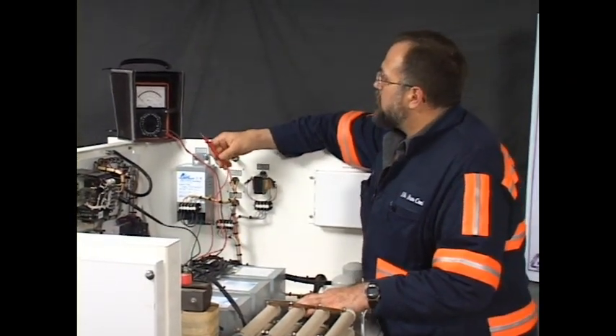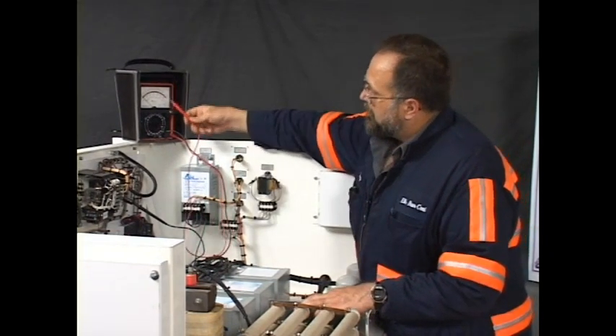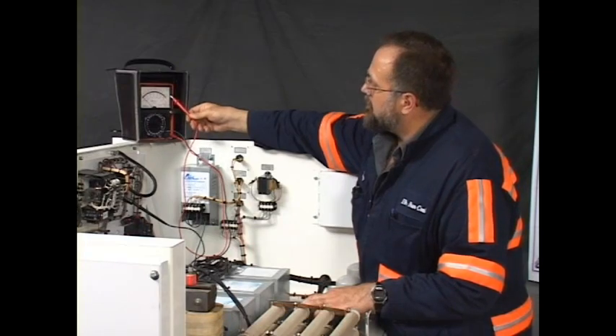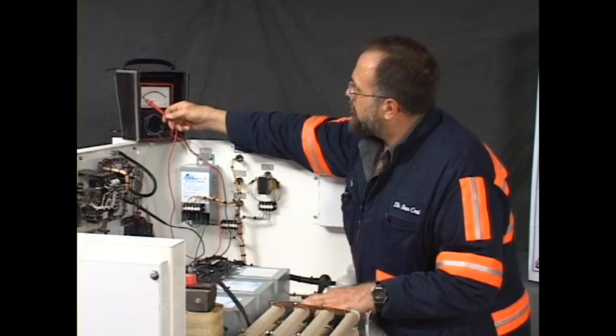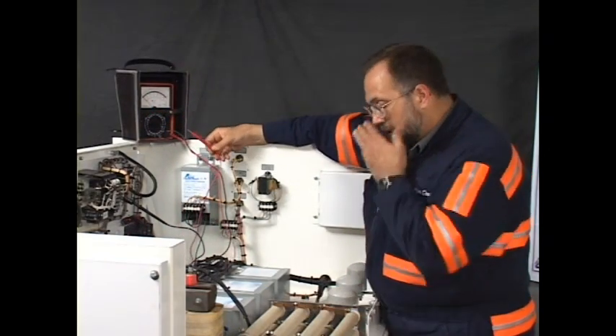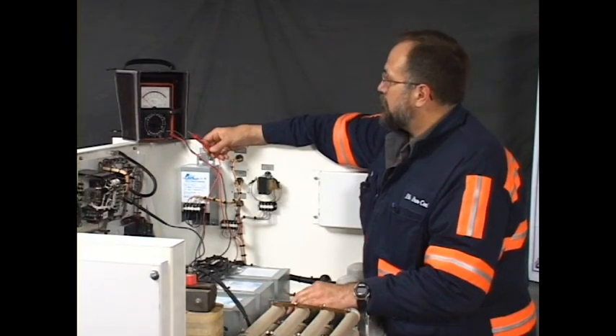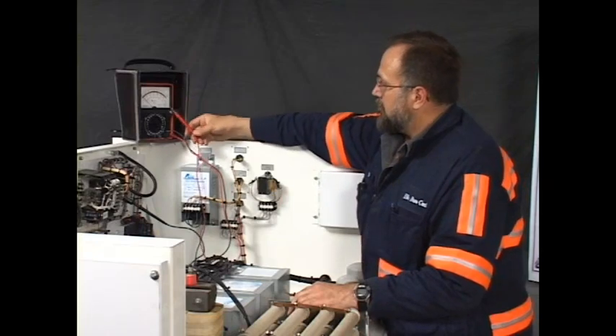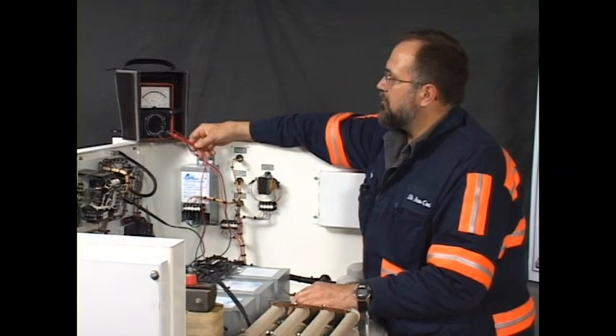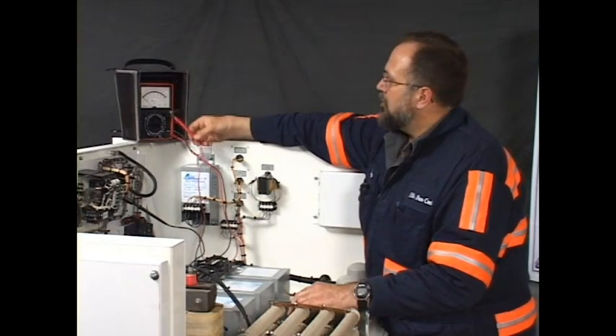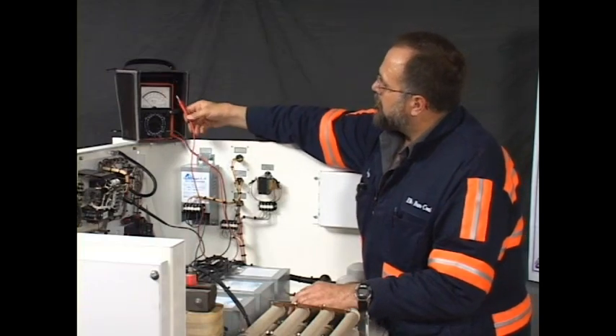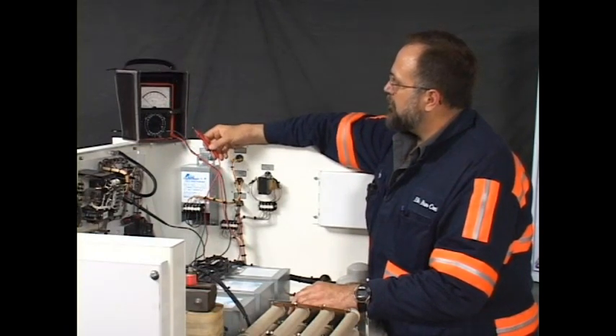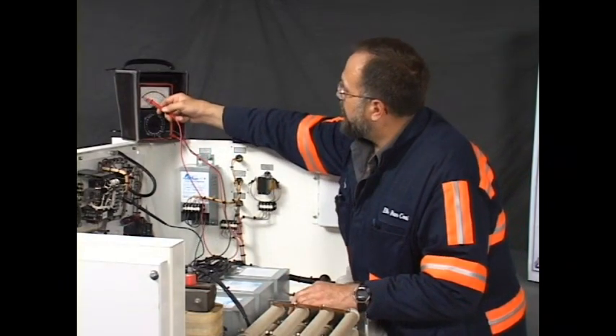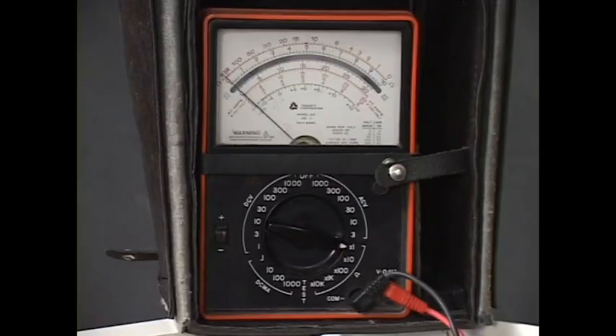Now, here's where we're going to use some of our meter reading skills. You can see on this top scale, they have a 0 all the way over here on the right and an infinity symbol all the way over on the left. These analog meters are not usually linear, in that the same distance of needle travel doesn't always have the same ohmic value at different points on the scale. From 0 to 1, about a half inch of needle movement for 1 ohm. From infinity, complete open circuit, to 500 ohms is about a quarter inch. Between 500 ohms and 100 ohms is about a half inch.